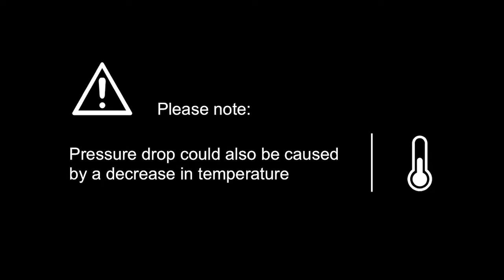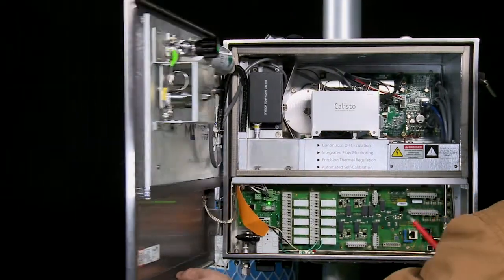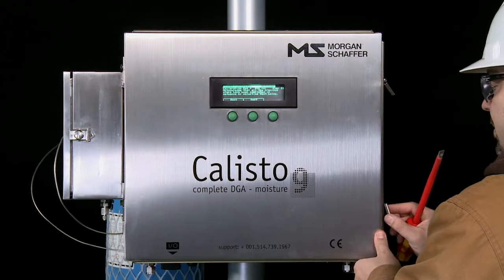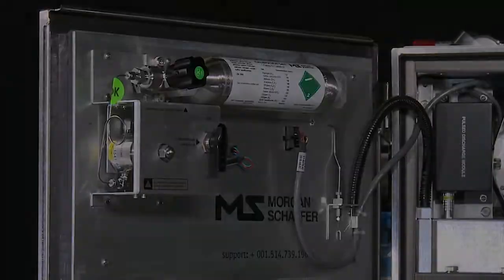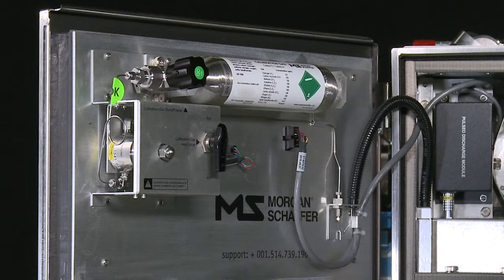Some care should be taken in interpreting the pressure drop errors as leaks, since they could be caused by a decrease in temperature of the calibration gas cylinder if the door is open. To be sure, close the door and wait to see if the error condition clears. Recommended wait times are 2-hour wait for the 1-hour drop error, 13-hour wait for the 12-hour drop error. This concludes the instructions for the replacement of the calibration gas module for Calisto models C500 and C900. Please remember to follow these instructions carefully and contact us if you have any questions.